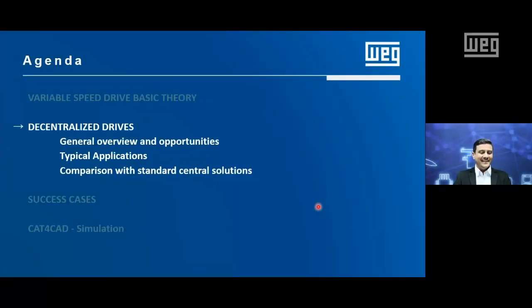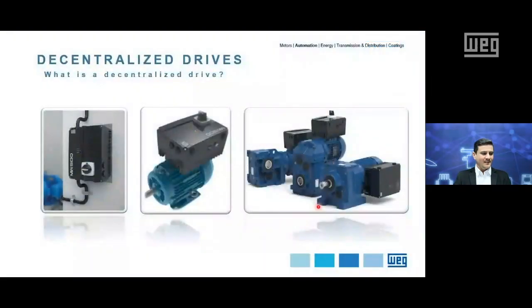So now let's enter into the decentralized drive section. What is a decentralized drive? A decentralized drive is designed to be mounted directly on the motor terminals or as close as possible to the machine. One of the main features of this type of VFD is the high degree of protection, for example, IP66. Therefore, depending on the environment where the VSD will be installed, the presence of dust or water, or in case the machine needs to be cleaned, this will not damage the drive.